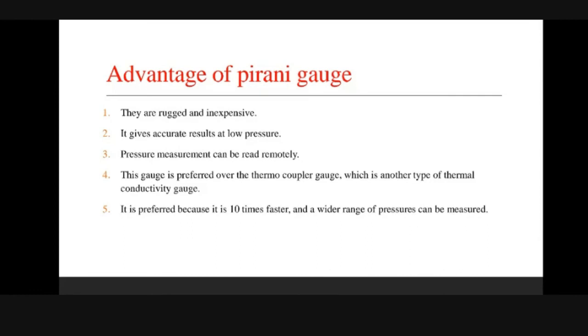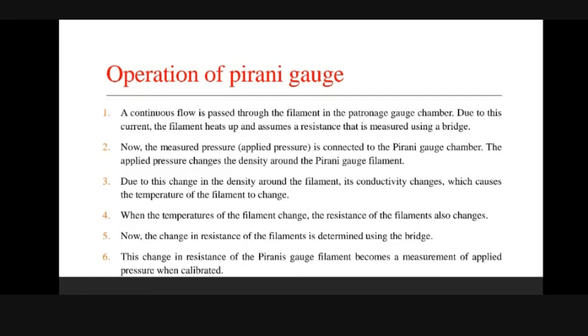Pirani gauge is preferred over the thermocouple gauge, which is another type of thermal conductivity gauge. It is preferred because it is 10 times faster and measures a wider range of pressure. Operation of Pirani gauge: continuous current is passed through the filament in the Pirani gauge chamber. Due to this current, the filament heats up and assumes a resistance that is measured using the bridge.